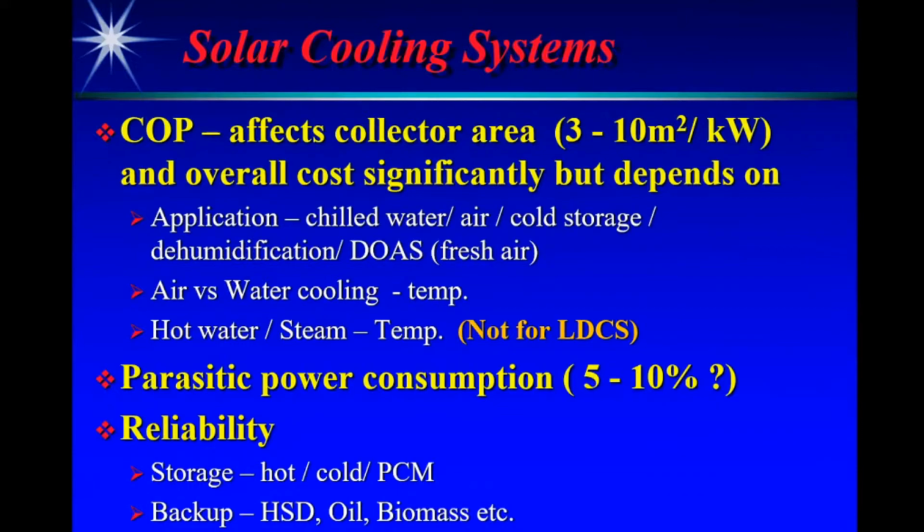Many of these systems, like the adsorption systems, can be either air-cooled or water-cooled. Again, the point is that we would require water in all these technologies. Then we have the parasitic power consumption, which is there in all these systems, which should be kept as low as possible, typically less than 5 to 10%. Reliability is also important. So maybe you have to not only store, but also have a backup.